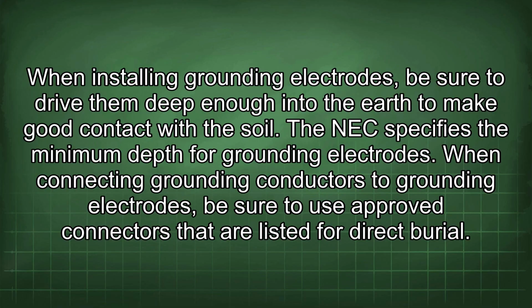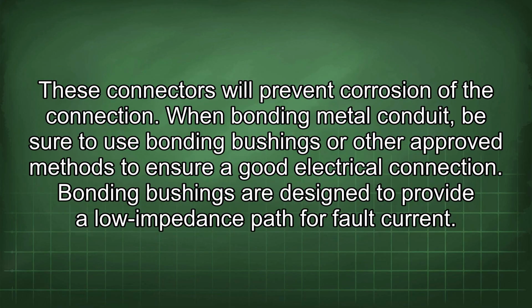When connecting grounding conductors to grounding electrodes, be sure to use approved connectors that are listed for direct burial. These connectors will prevent corrosion of the connection. When bonding metal conduit, be sure to use bonding bushings or other approved methods to ensure a good electrical connection. Bonding bushings are designed to provide a low impedance path for fault current.